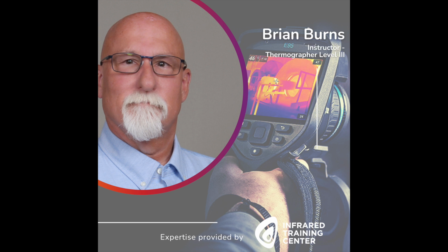So many potential inspection targets that we've got to also keep in mind is cells that are degraded. Whether or not we've got broken bypass diodes within the system, delaminations and cracks in the glass, moisture intrusion, and you'll be able to pick that up very easily. And I'd mentioned already about bird droppings and shadowing. And that glass itself is pretty robust, but sometimes that can even be damaged by the acid or something getting onto it, fuel. If you've got tractors nearby, maybe diesel fuel being spewed out and just with droplets onto the glass.